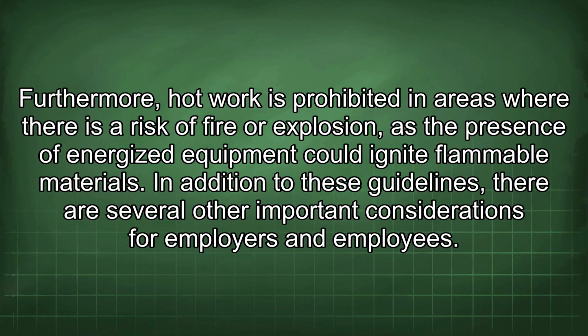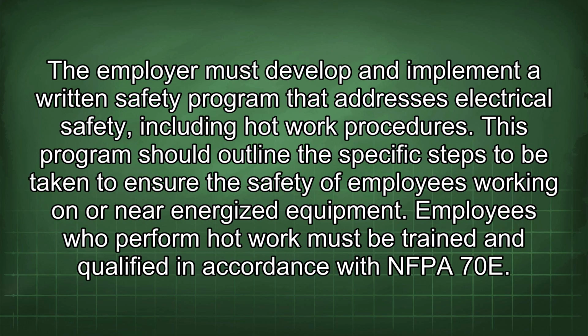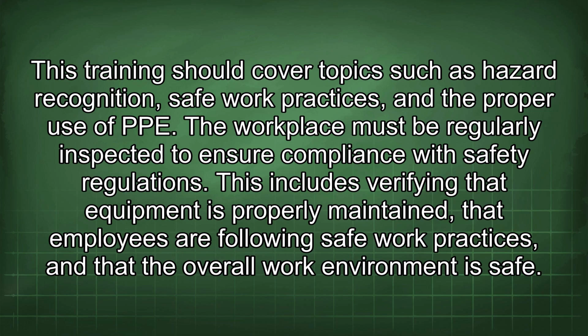In addition to these guidelines, there are several other important considerations for employers and employees. The employer must develop and implement a written safety program that addresses electrical safety, including hot work procedures. This program should outline the specific steps to be taken to ensure the safety of employees working on or near energized equipment. Employees who perform hot work must be trained and qualified in accordance with NFPA 70E, covering hazard recognition, safe work practices, and the proper use of PPE.